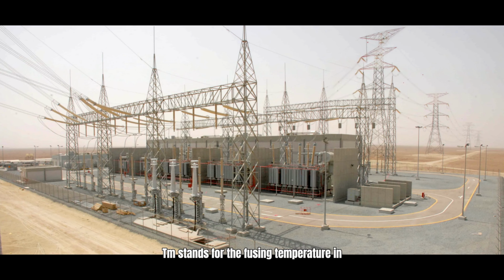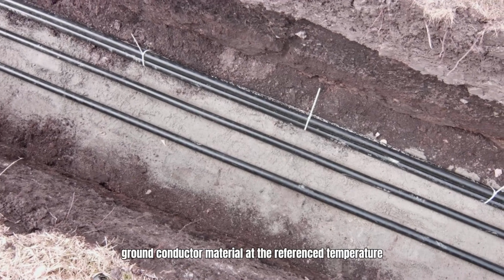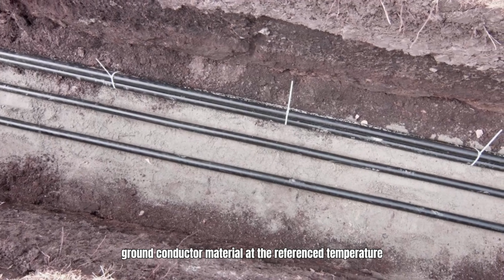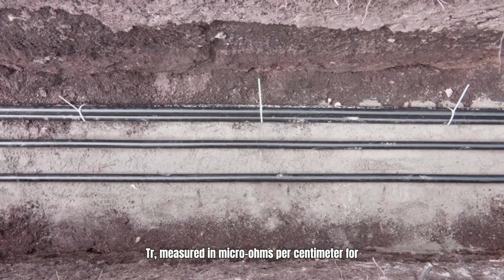Tm stands for the fusing temperature in degrees Celsius, representing the absolute maximum allowable temperature that the conductor material can safely reach during a fault. Ta denotes the ambient temperature in degrees Celsius, while alpha_r is the thermal coefficient of resistivity for the conductor material at the reference temperature Tr. Rho_r refers to the resistivity of the ground conductor material at the reference temperature Tr, measured in microohms per centimeter for accuracy.